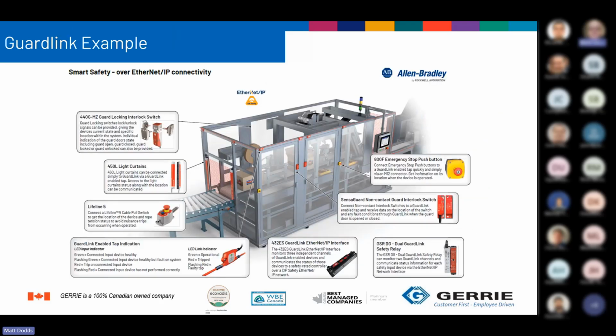So here's an application out of the brochure. Again, they're showing a cartoner with a variety of doors, e-stops, and light curtains. Basically, if I trip a device, the machine shuts down. It's a perfect application for GuardLink because all the devices reside on the same link, and if any of those devices go down on that link, it turns off the outputs.